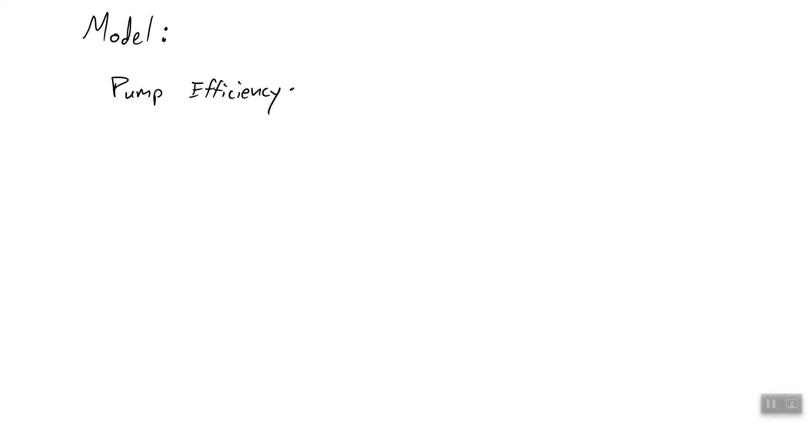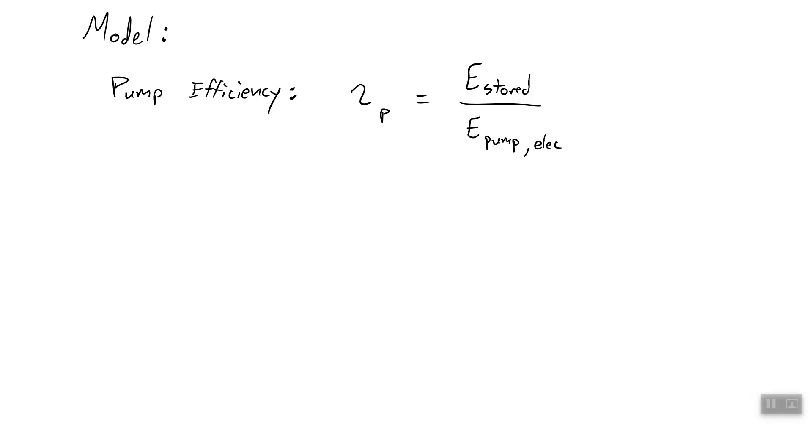So okay, the modeling we're going to get into today is very basic. In fact, we're just going to talk about efficiencies. So as you pump this water up the hill, you do so at a loss, which we will call the pump efficiency. The pump efficiency tells us how much energy we actually store. So the energy stored compared to the amount of energy that we sent to the pump. This would be the electrical energy we sent to the pump. So this accounts for losses in the pump itself, losses in the piping system, moving the water uphill. All of these different losses gives us a total pumping efficiency, a kind of a storage efficiency.